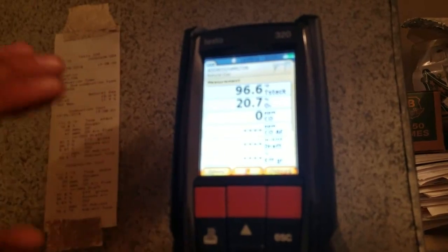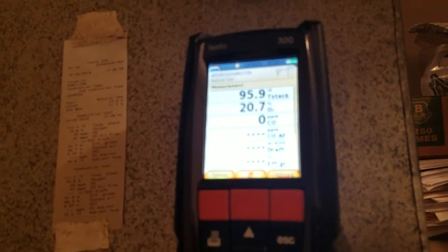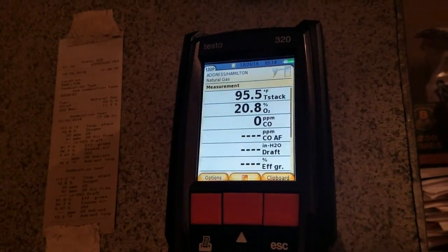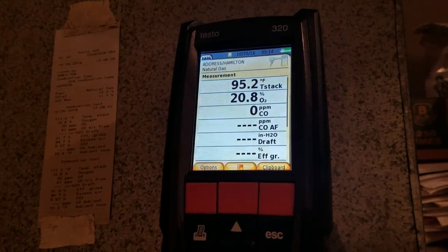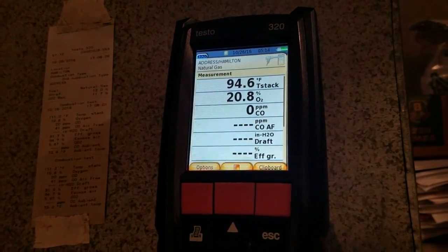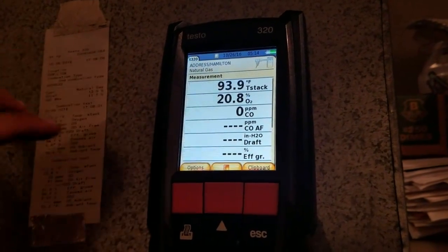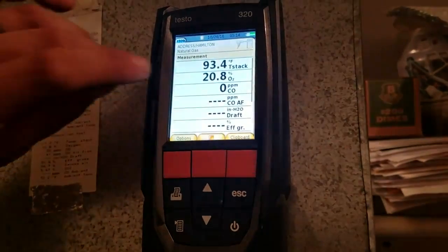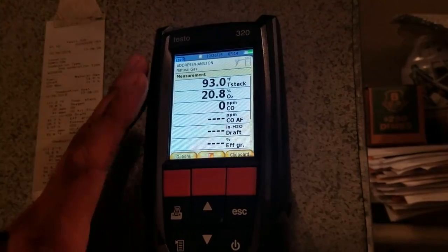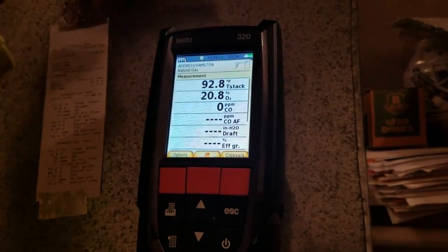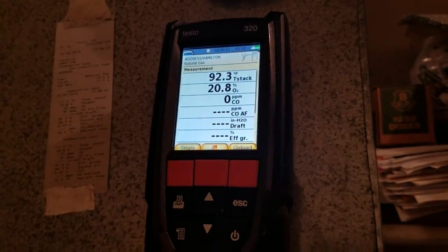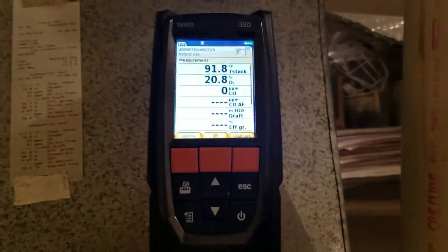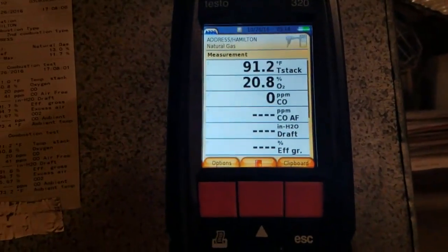Now, when the fan on your unit turns on, it pressurizes the heat exchanger itself. If it had a crack or a bad spot in it where it's rusted, the pressure of the air going through the ductwork is going to get in through that hole. So this number will start to rise. So we're going to watch the complete combustion cycle here from when it starts to where when we have pressure around the heat exchanger, and also once it's stabilized.